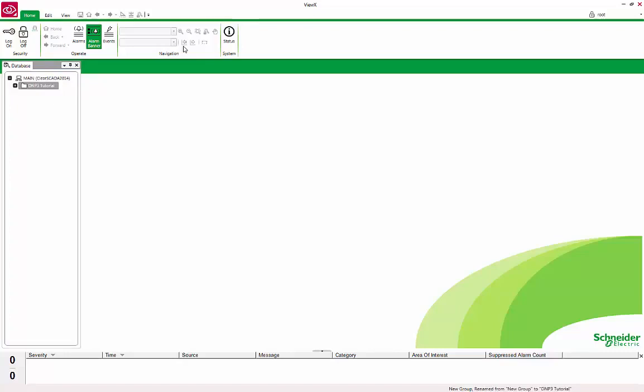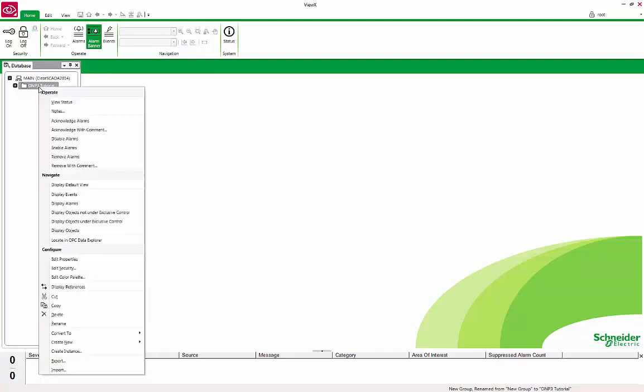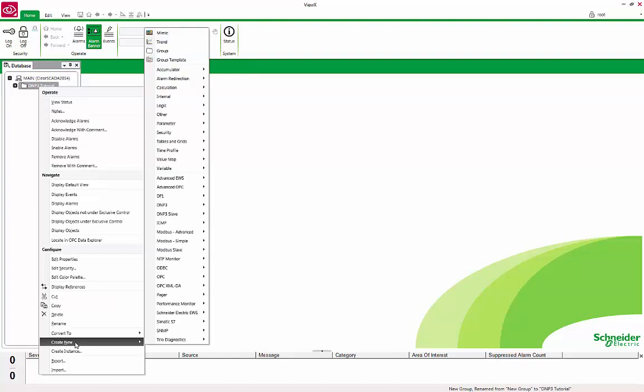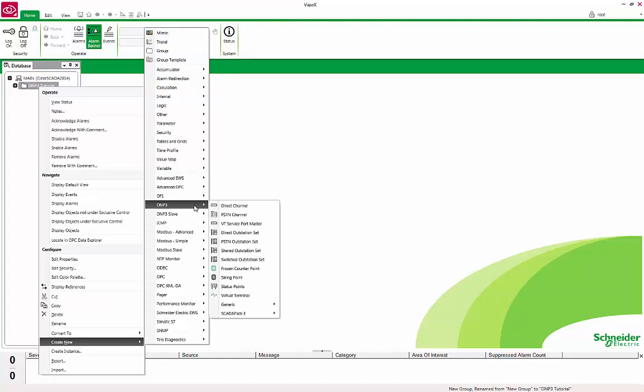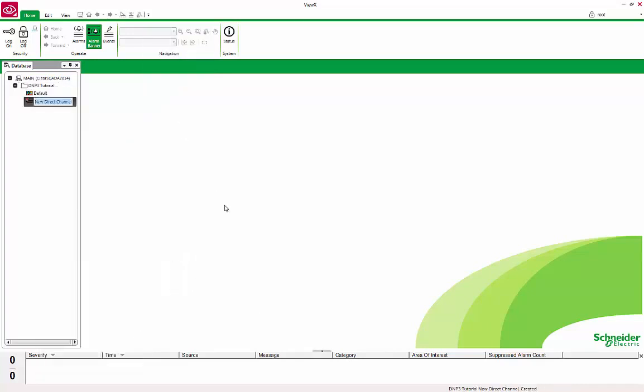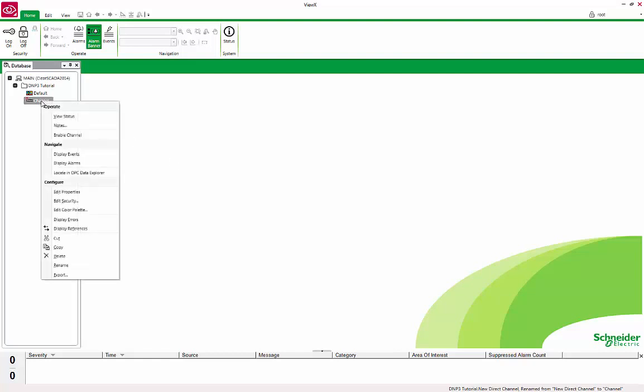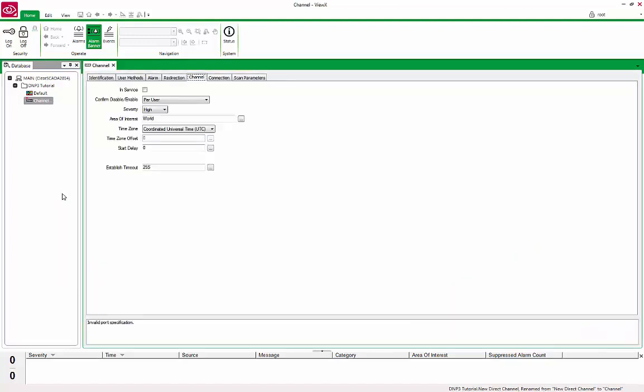The first object to create is a DNP3 Direct Channel. The channel object relates to the communication method, serial or IP, that ClearSCADA will use to communicate with the device. Right-click on the DNP3 Tutorial, Create New, DNP3, and select Direct Channel. Rename it to Channel. Double-click on the channel to open the Properties form. Under the Channel tab, check the In Service box to make the channel active.